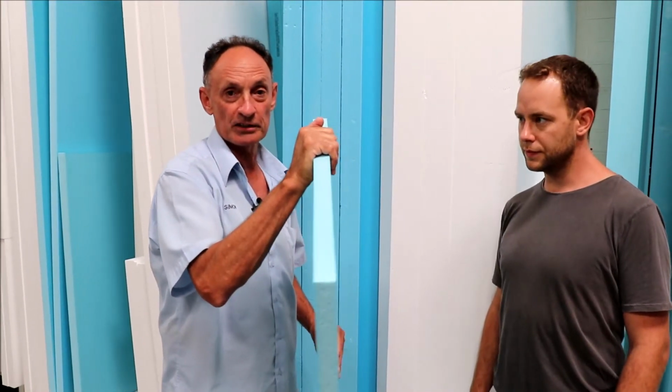Simon, let's talk quickly again about the thicknesses of the extruded polystyrene. I believe you have some pieces over here to show us the difference between the two recommended thicknesses. Yeah, so polystyrene XPS boards for underfloor insulation come in a range of thicknesses from 20 mil through to 100 mil. But in Western Australia, for underfloor heating, we recommend in the Perth region that you use a 30 mil sheet, 30 mil thick. That is this sheet here. You can see the thickness there.